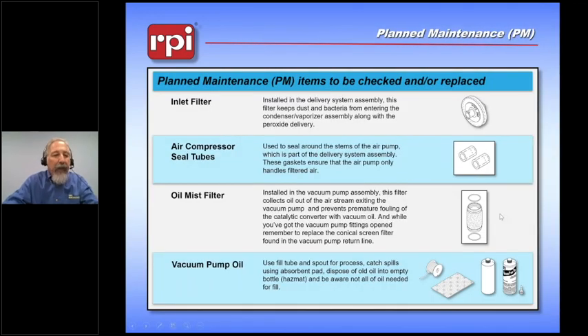So again, what do we have included in these planned maintenance kits and why are we checking them? Well, way back at the very beginning of the system, we talked about how the hydrogen peroxide was transferred from the cartridges into the vaporizer condenser using sterile air. And this is the sterile air filter that prevents any contamination from flowing in with the hydrogen peroxide. There are also tubes that keep the valves seated properly within the vaporizer condenser assembly, and there is a pump in there as well.